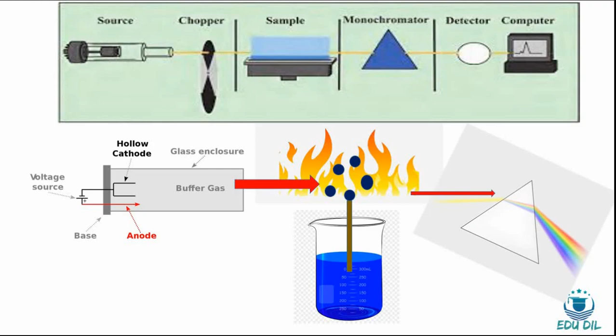So by keeping a slit in here, you can separate out your wavelength of interest, and you can put that beam into this detector, and finally you can take the concentration or the absorbance using a computer application. Now this is the instrument, the atomic absorption spectrometer. As I mentioned, this is the sample. Through the nebulizer, this sample moves into the burner head.